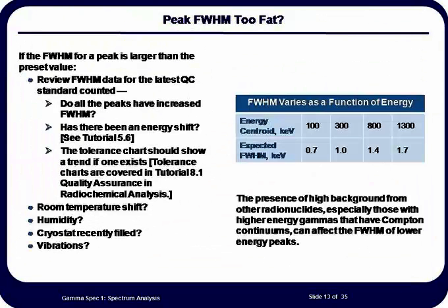The table at the right shows the expected full-width half maximum for a certain detector at various energies. This was determined during the detector's initial calibration. Once a sample count is completed, the software determines this among other parameters. It will take the energy of the peaks found, calculate a theoretical full-width half maximum, and compare this to the actual full-width half maximum. If the measured value is a pre-selected value beyond the theoretical value, the software will flag the peak as having a poor shape.